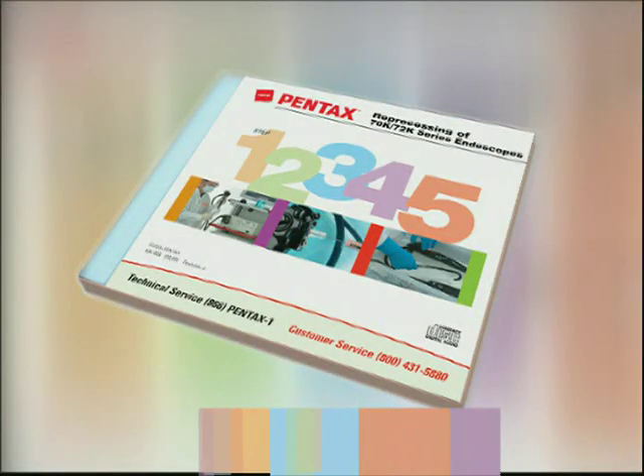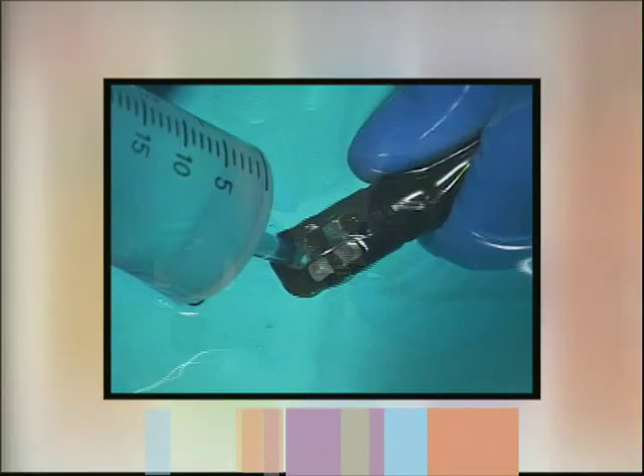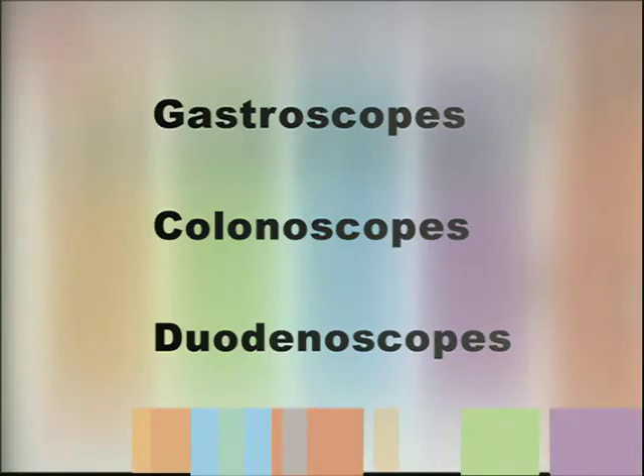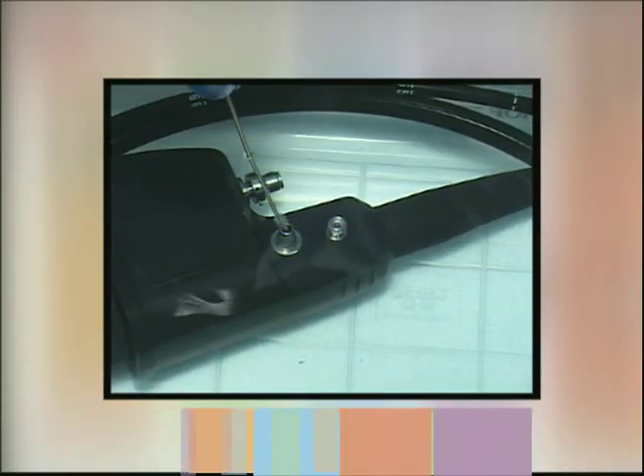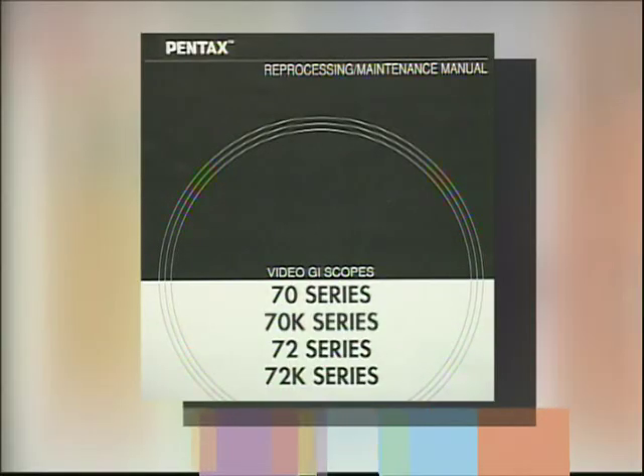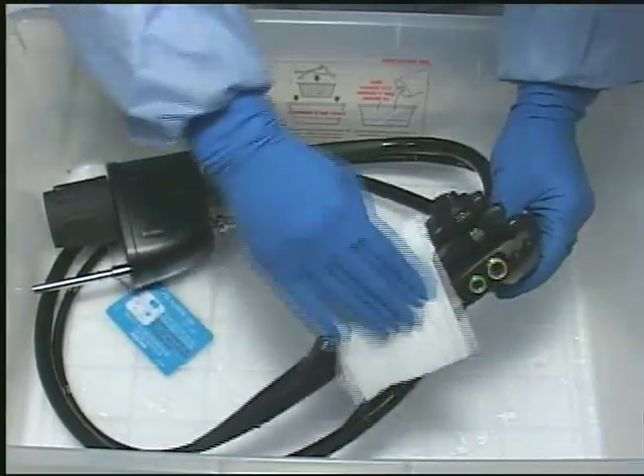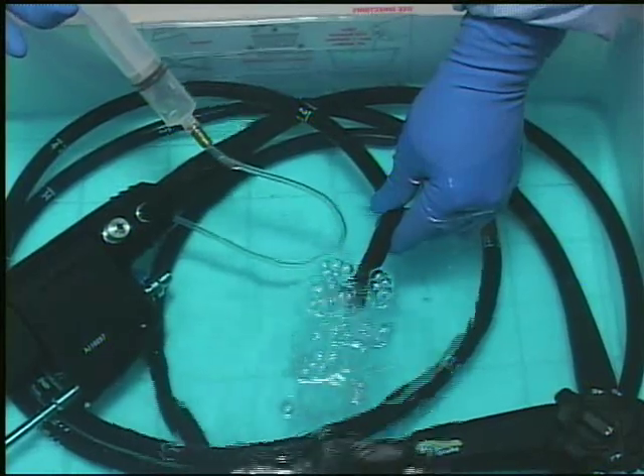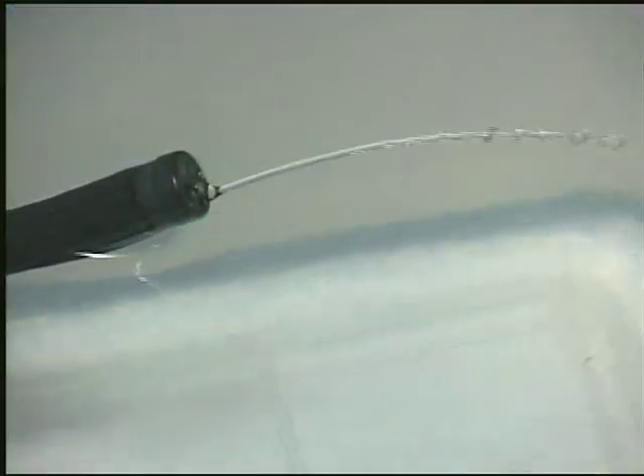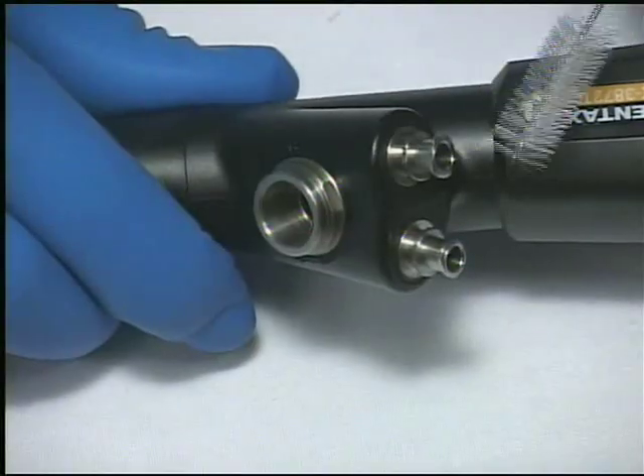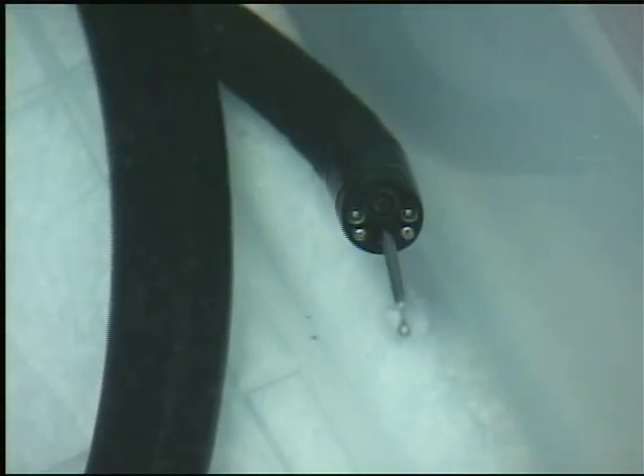This educational video is intended to provide guidance to healthcare professionals on the manual cleaning and high-level disinfection of Pentax gastroscopes, colonoscopes, and duodenoscopes. The demonstrations in this video are meant to supplement but not replace the complete and detailed reprocessing instructions contained in the reprocessing maintenance manuals supplied with each Pentax endoscope. Proper cleaning and high-level disinfection processes must be performed prior to each and every procedure to maximize the performance of the endoscope and to minimize the risk of contamination from pathogenic microorganisms.